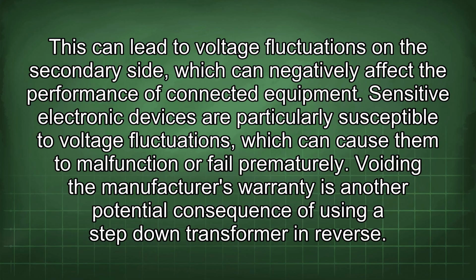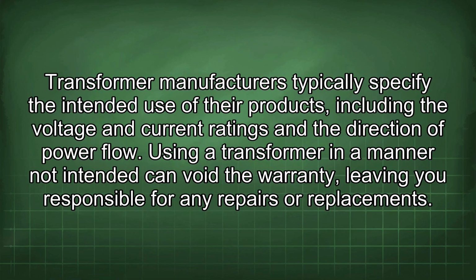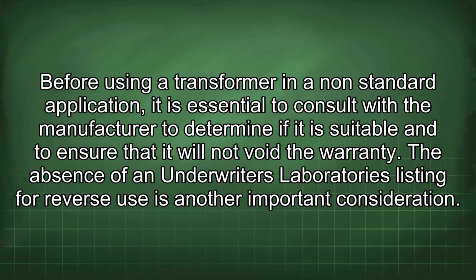Voiding the manufacturer's warranty is another potential consequence of using a step-down transformer in reverse. Transformer manufacturers typically specify the intended use of their products, including the voltage and current ratings and the direction of power flow. Using a transformer in a manner not intended can void the warranty, leaving you responsible for any repairs or replacements. Before using a transformer in a non-standard application, it is essential to consult with the manufacturer to determine if it is suitable and to ensure that it will not void the warranty.